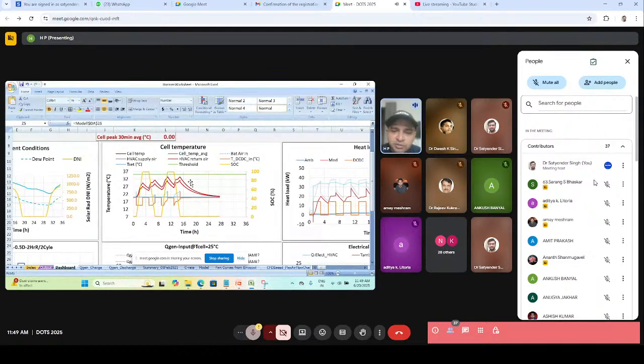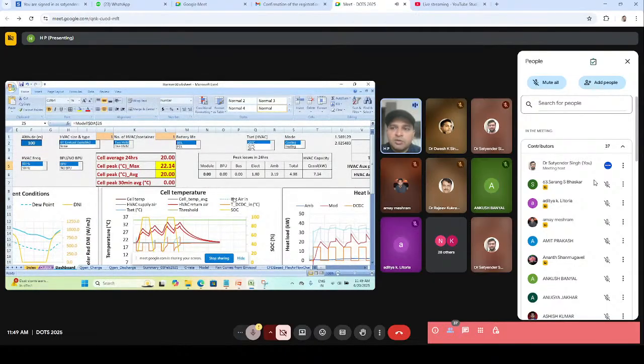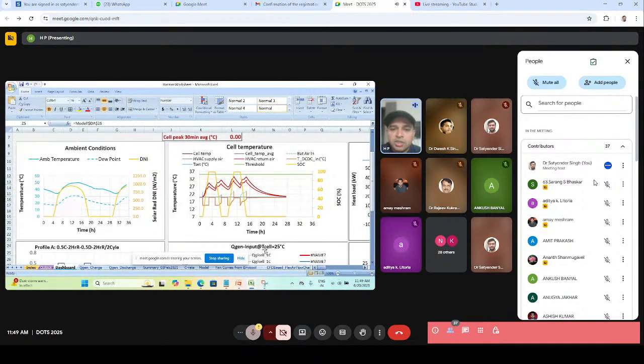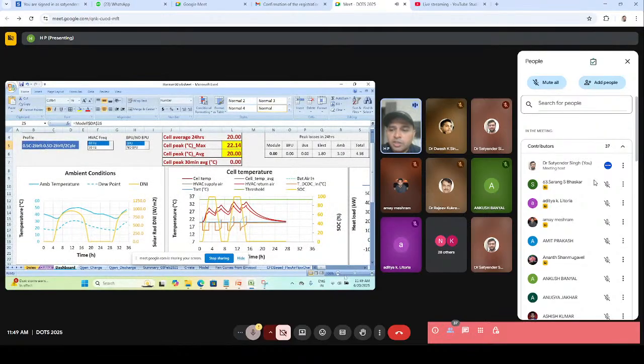Generally when you read more about it, people refer to it as the hourly application. For a 2 hour application, I know the power that must flow through the equipment, and for that power, what current will go through the conductors, basically the cells, and how much heat it would generate. That can be calculated using the simple formula I squared R, although it's not that simple, as there are some characterizations that happen. This model particularly shows how my ambient conditions are regulating.